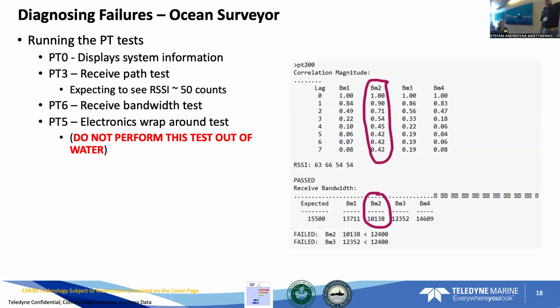So the PT3 and the PT6 are both receive tests. They're looking for electrical noise. They're not putting any noise out, so it's not going to damage your transducer. But what you see is the lags, the correlation doesn't drop, and it should drop. Once it's at lag 5, it should be down to almost 0. If it doesn't drop, then there's a failure. The other, on the PT6, the second test, it should be 20% plus or minus of the expected noise. And you can see we're pretty low here on beam 2. So we're getting noise on beam 2 and then some on beam 3, but mostly on beam 2.